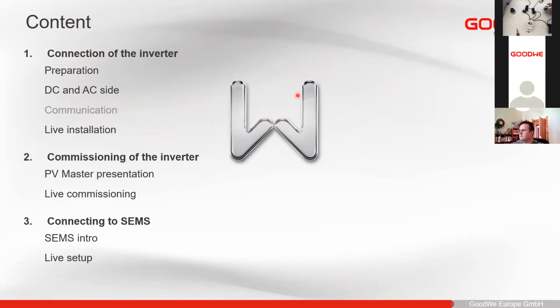So the CTs should then, after they're connected to the inverter via this. So actually I can connect it now just for demonstration purposes. You just connect it in here. Click. And then the CTs here are connected just before the grid connection point. And the voltage sense coming here on the bottom side needs also to be next to the CTs. So there should be no loads in between, because then it won't measure the power properly.